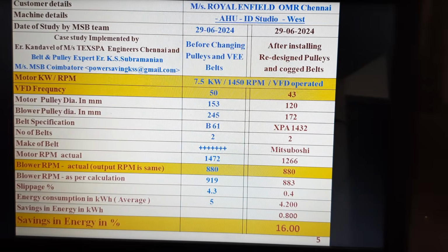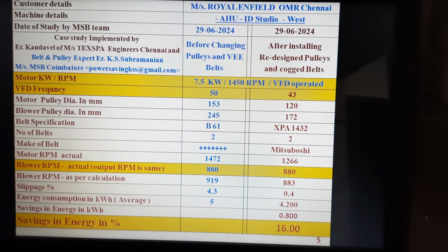Coming to the case study, you can see it is an automobile major based at Chennai, and it was done on an air handling unit in the year 2024 by our team. It is a 7.5 kilowatt motor, VFD operated. You can see the before study, before replacing the belts and pulleys: at 50 Hz the blower RPM is 880 and the energy consumption is almost 5 kilowatts. After redesigning the belts and pulleys, the motor is operated at 43 Hz, but the blower RPM is maintained at 880.